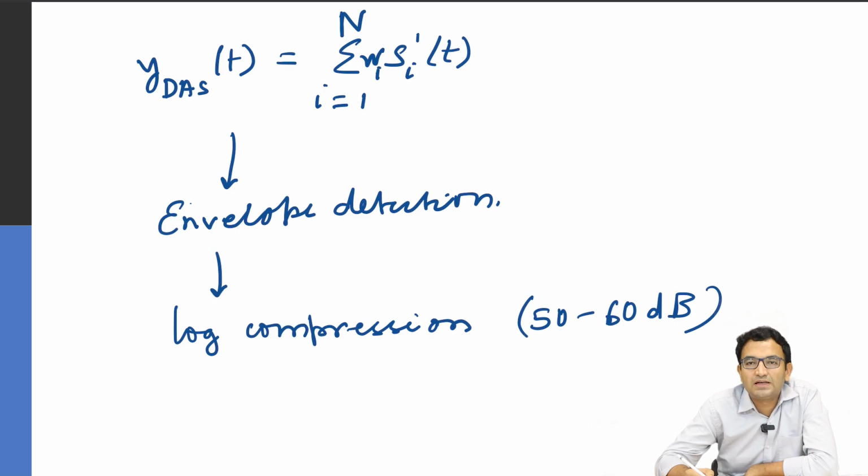For example, contrast enhanced imaging, typically when you're using nonlinear imaging, typically uses lower dynamic range because the majority of the dynamic range is occupied by the linear signal, which gets cancelled off. So the remaining signal occupies a lower dynamic range. Okay.